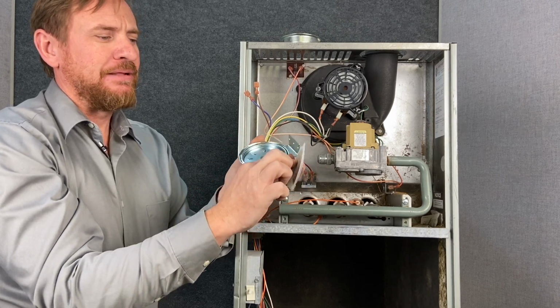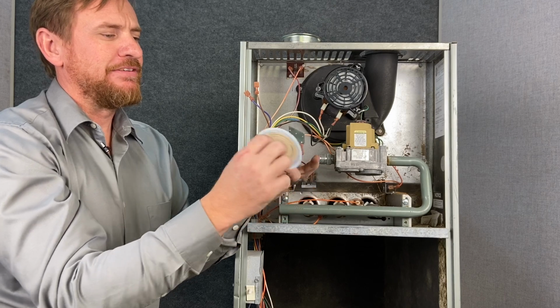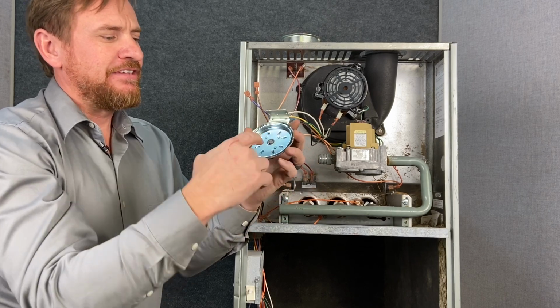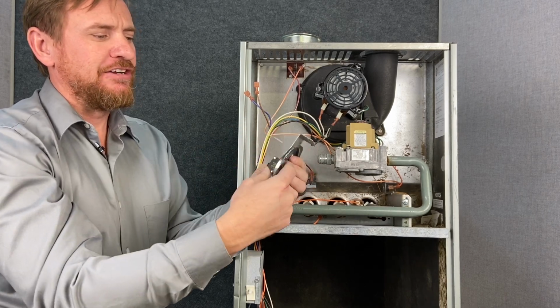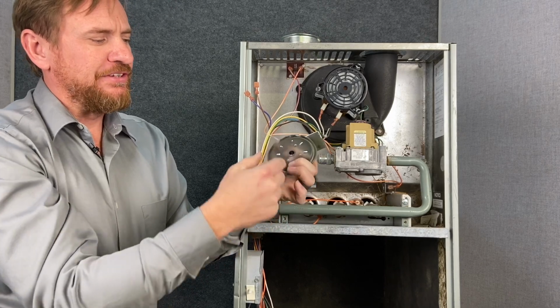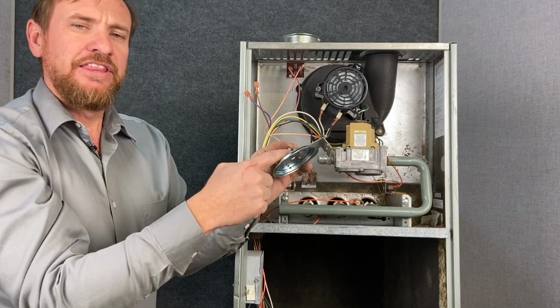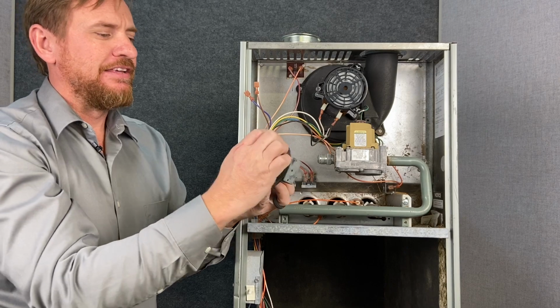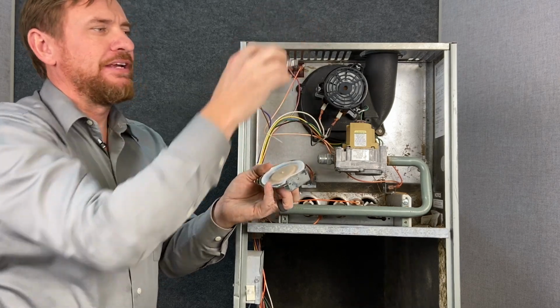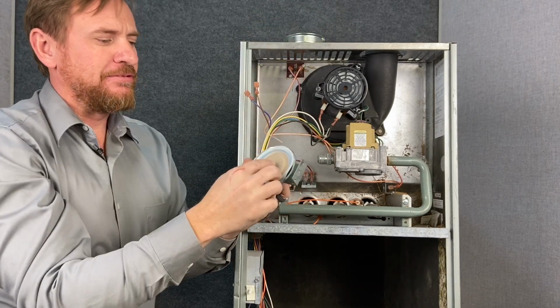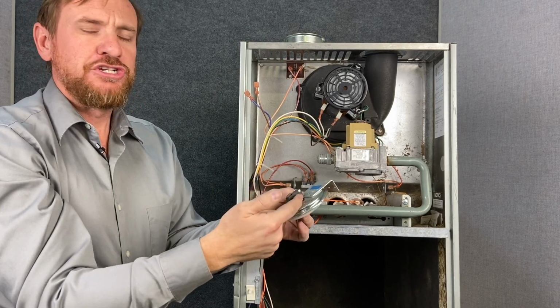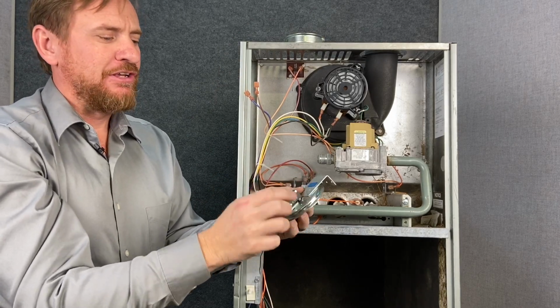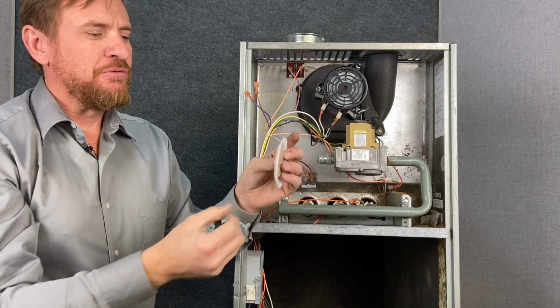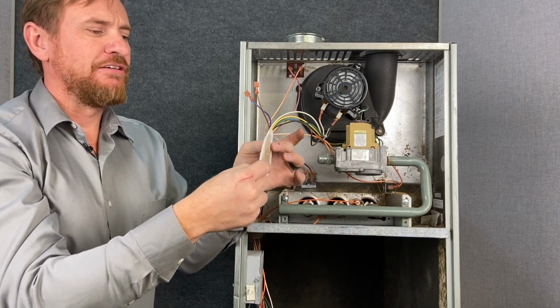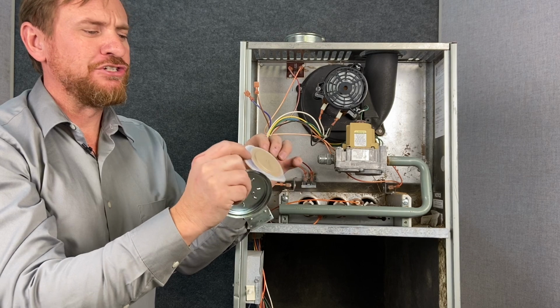So this center plastic is metal. This is a rubbery type material, membrane, and this keeps pushed on right here. So when it pulls a vacuum, it pulls this down, and this switch then closes. And when the vacuum stops, the spring pushes this back in, and that keeps the switch pushed open. So we pull a vacuum and it closes. Very simple. This is usually what wears out internally. You don't repair this, you just replace it. Just wanted you to see what it's like.